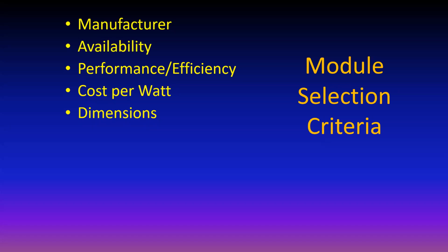So at 0.5 volt each, a 60 cell module operating at full power will be putting out about 30 volts. That's not a whole lot, but when you put 10 of them in series, then you get 300 volts. Put 20 in series, you get 600 volts. So you can get pretty high voltage by just stringing these out in series. Thermal performance is important because as it gets colder, these things actually produce more electricity and their output voltage increases. As it gets hotter, they produce less electricity and their output voltage decreases. So you need to take that into account in your system performance analysis.